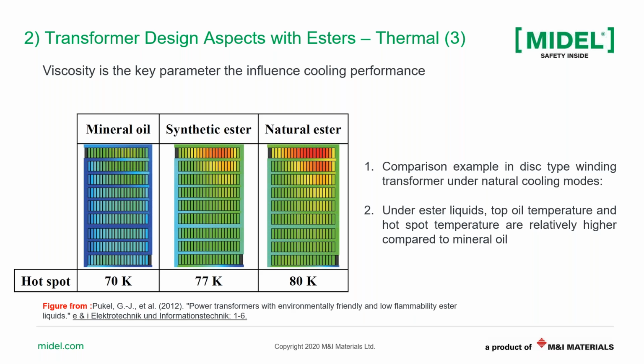The researcher there compared mineral oil, synthetic ester, and natural ester. And what we focus on here is the hotspot temperature. Of course, just to clarify the images, these are one pass in a disk type transformer. You can see here the disks, and between them you have cooling ducts allowing the liquid to circulate and cool them. You can see mineral oil, the hotspot temperature is 70 Kelvin rise because it has lower viscosity than esters.